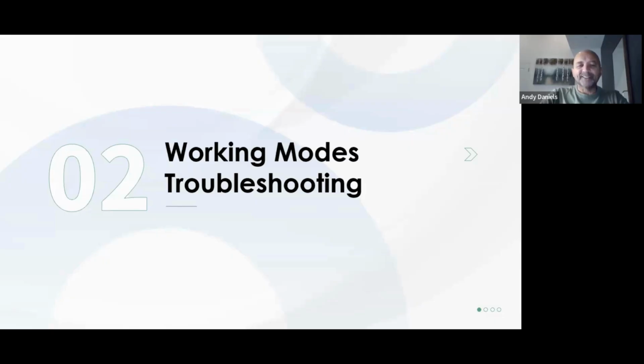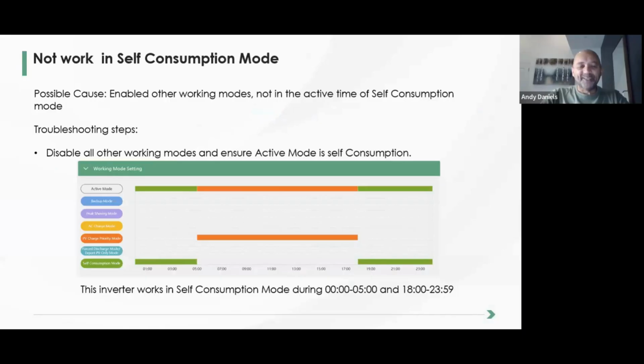Right, working modes and troubleshooting. Don't laugh at me, Tatum. Working modes and troubleshooting. Right, so the possible cause of not working in self-consumption mode. What are the possible causes? That you've got other working modes enabled, and it's not in the active time of self-consumption mode.